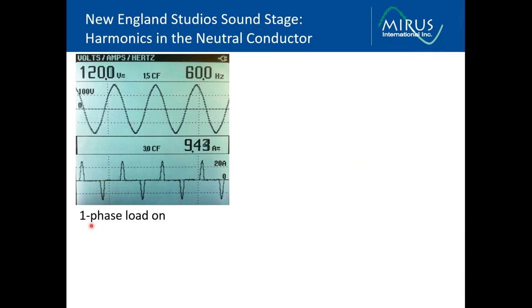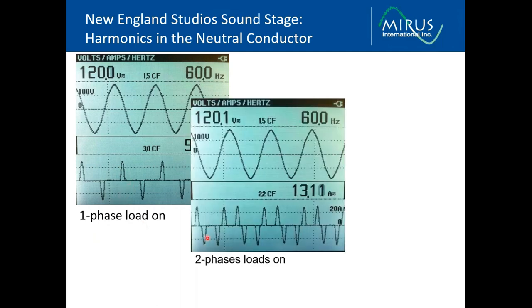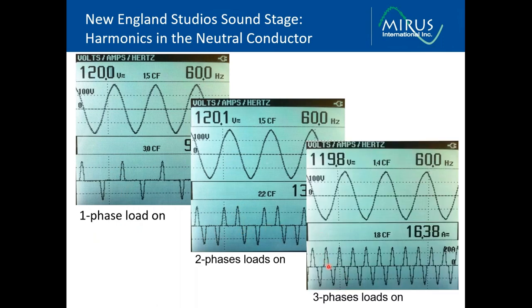When one phase was turned on, the lights drew a single pulse of current measured in the neutral. When they switched on another phase, it added another pulse on the neutral. And when they turned on the third phase, it added the third pulse. So you can see that we ended up with the third harmonic in the current. The phase current ended up being much less than the neutral. The neutral current ended up being much more than the phase current.